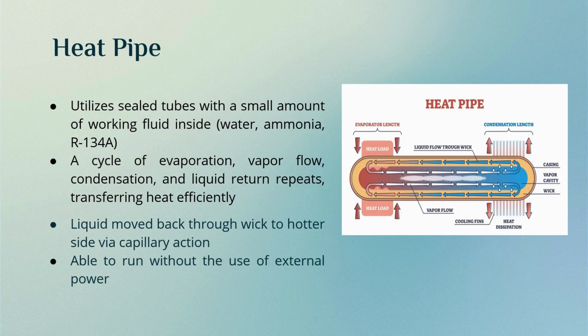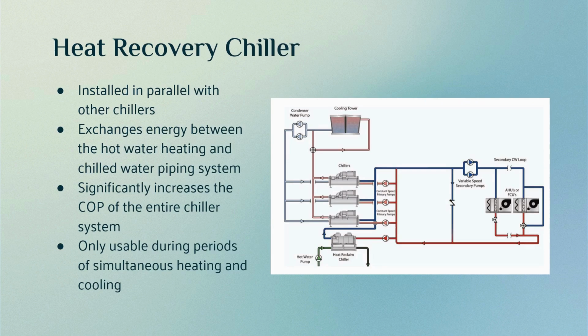We also have a heat pipe, which utilizes sealed tubes with a small amount of working fluid through a cycle of evaporation, vapor flow, condensation, and capillary action in order to achieve heat transfer. However, this system does not have as high heat transfer effectiveness, but it is able to run without the use of external power. Finally, for water-to-water energy recovery, we looked into a heat recovery chiller, which is installed in parallel with other chillers and exchanges energy between the hot water heating and chilled water piping system, significantly increasing the coefficient of performance for the entire chiller system.